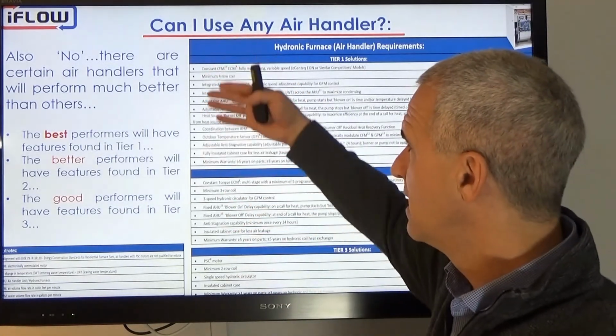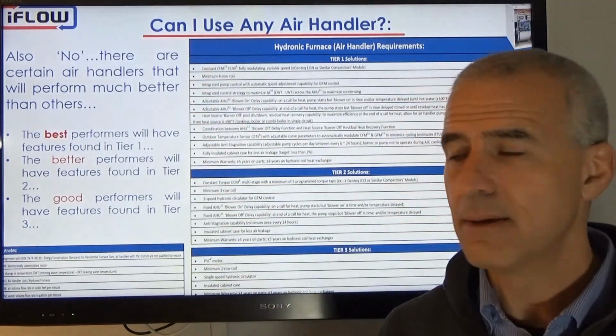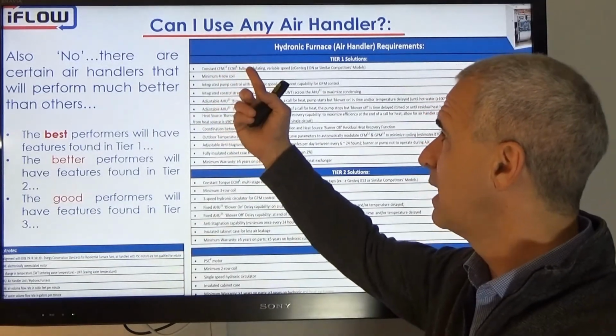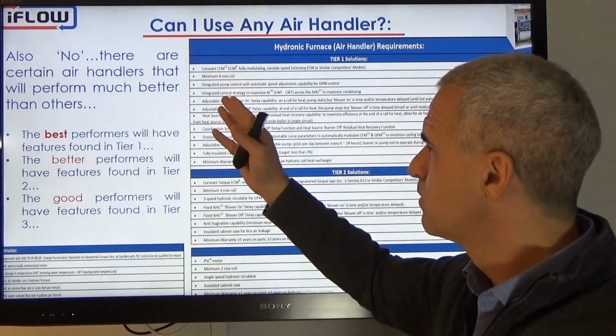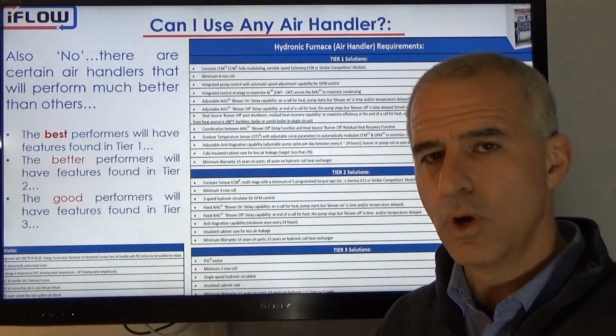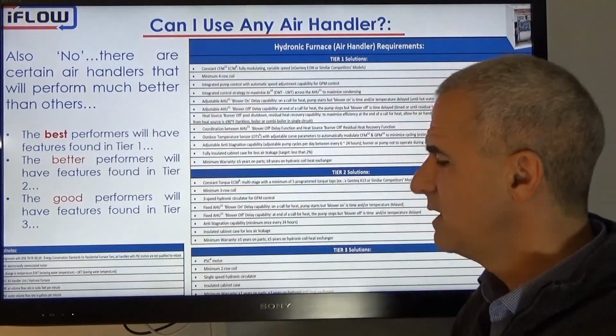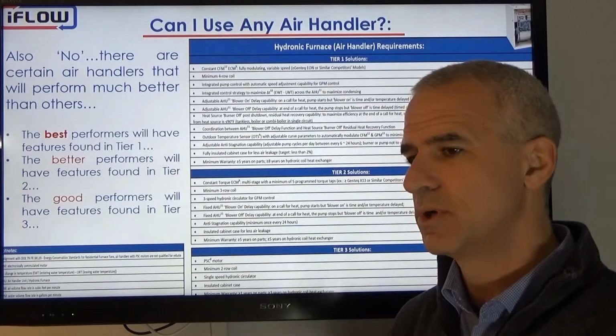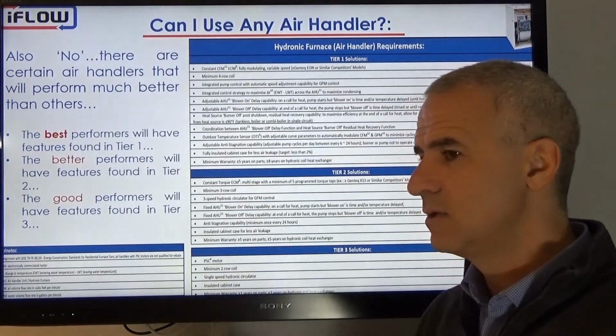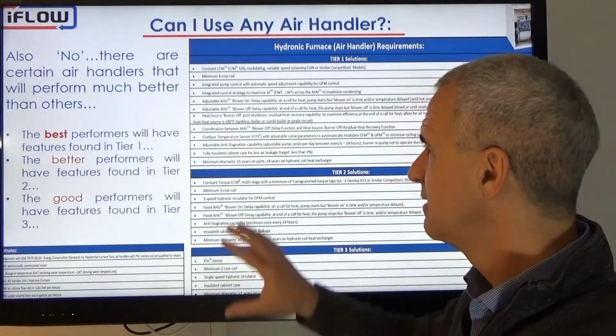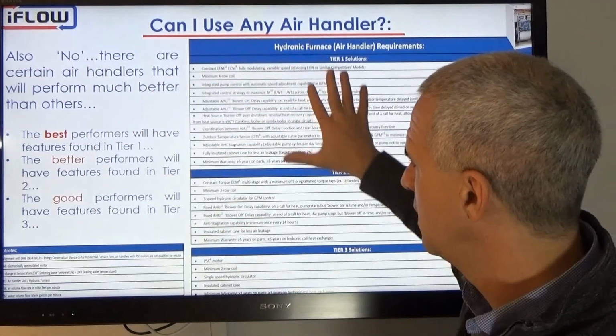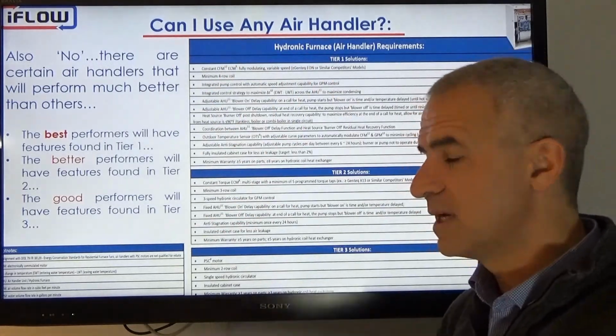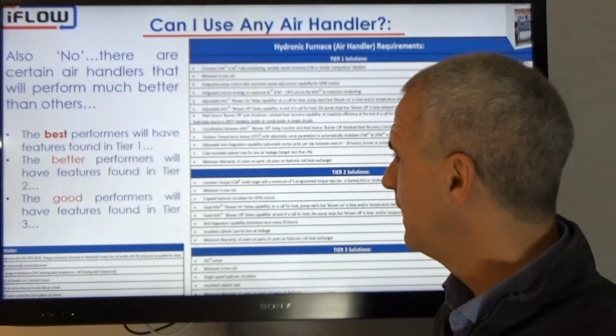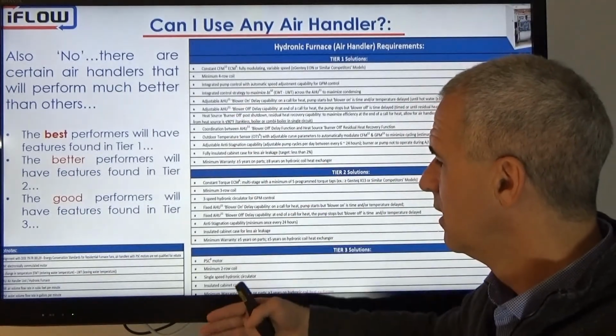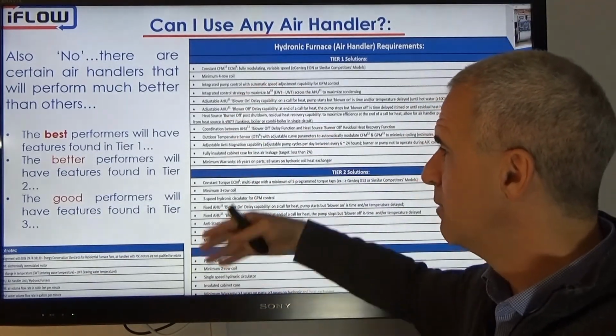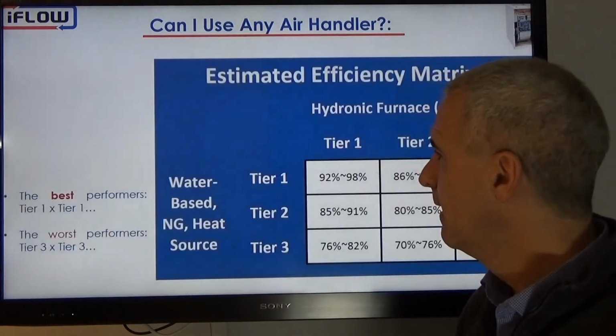As you get into more advanced control, so a constant CFM ECM controller with a minimum of a 4-row coil, with integrated delta T control, with pump control. We get into some advanced technology, and I'm not going to go through all of it here, but it's written here. It's on our website if you want to dig into it.